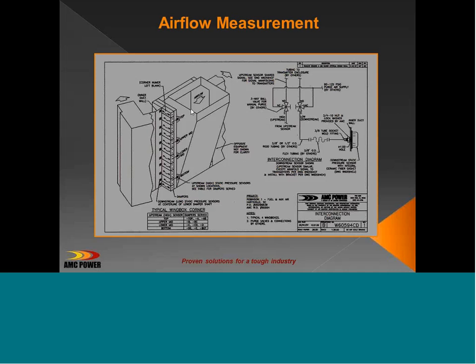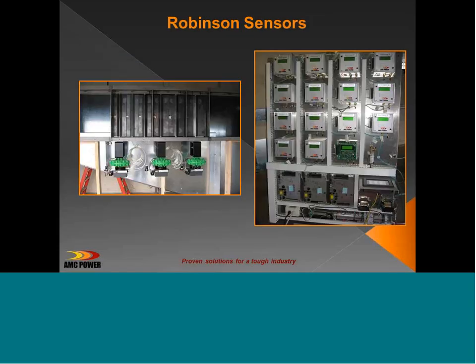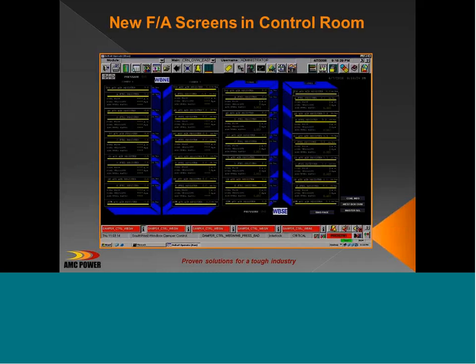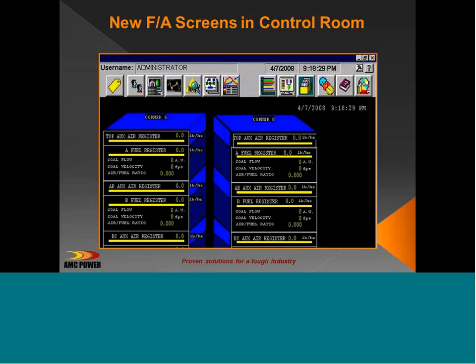So again, there's the static pressure measurement. This is our wind tunnel in California where we are mocking up a specific corner for a customer. And then we develop control room screens. Again, much like the wall-fired units, this is a corner-fired unit where we're measuring air-to-fuel ratio for each aux air and fuel air compartment. And again, the dampers can be modulated to give equal or biasing.